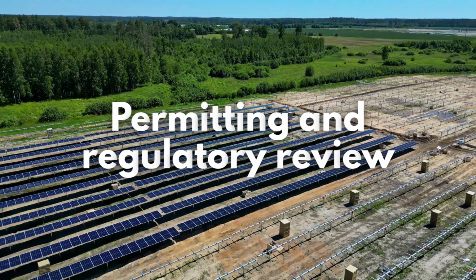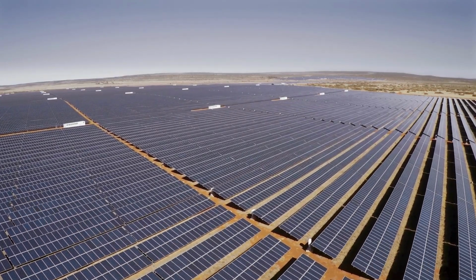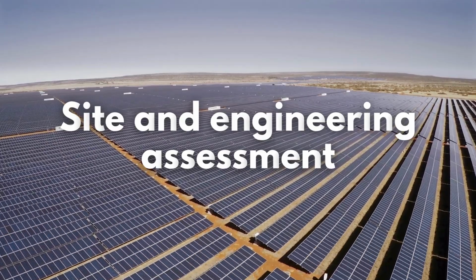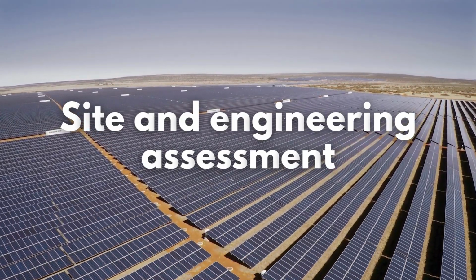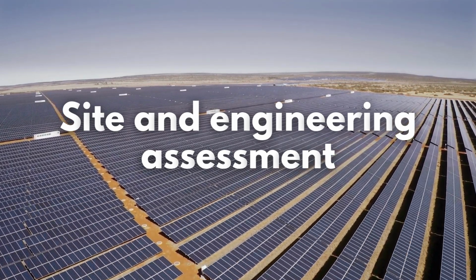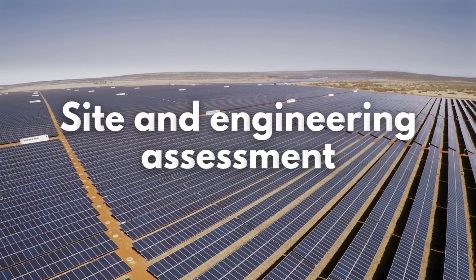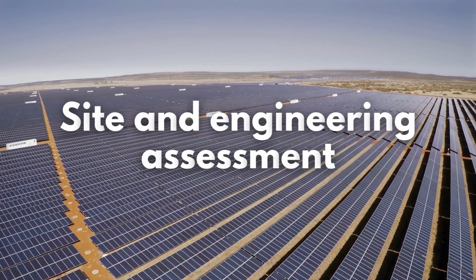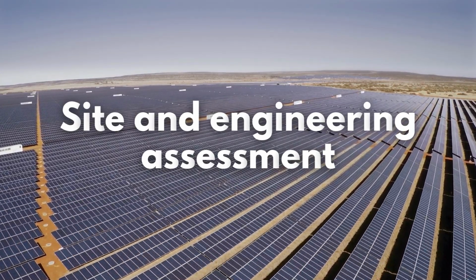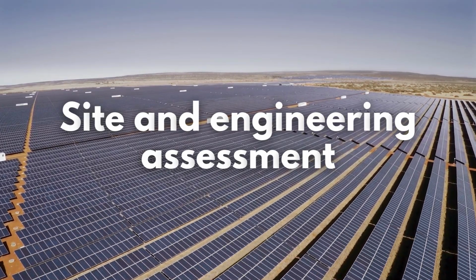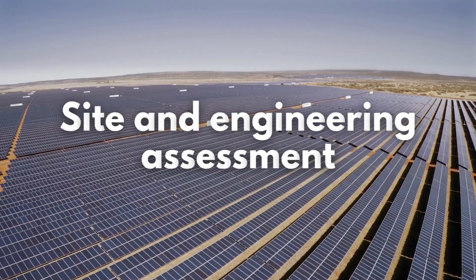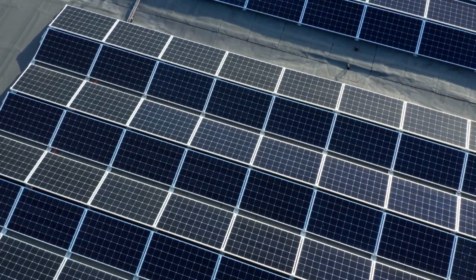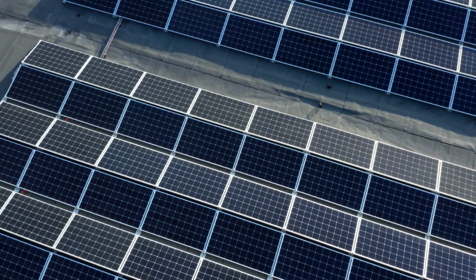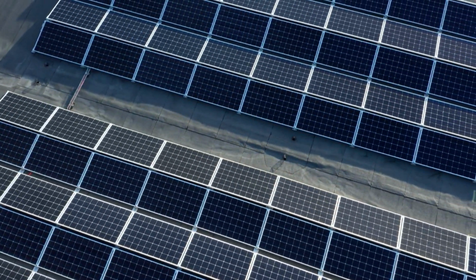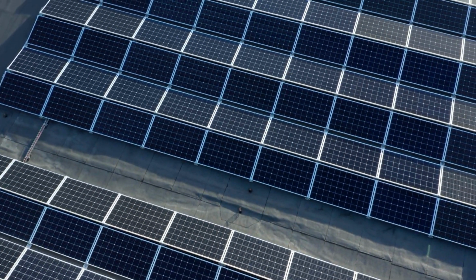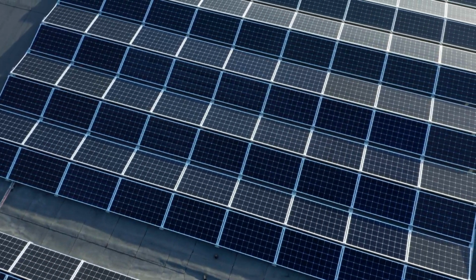The next important pillar is the site and engineering assessment. Here, the technical advisor reviews the physical characteristics of the site: topography, geotechnical conditions, flood risks, access roads, and constraints such as protected areas or archaeological zones. On the engineering side, the advisor checks the overall plant design, layout, electrical architecture, DC/AC ratios, string configuration, substation design, and evacuation infrastructure. The objective is to confirm that the design follows recognized industry standards, is suitable for the site conditions, and does not embed hidden constructability or performance risks.